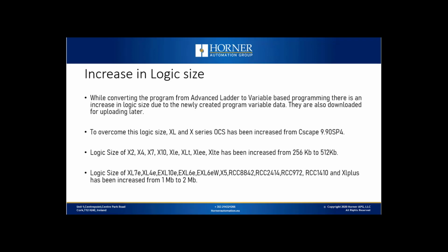While converting the program from Advanced Ladder to variable-based programming, there is an increase in logic size due to the newly created program variable data. They are also downloaded for uploading later. To overcome this, the logic size of XL and X series OCS has been increased from Cscape 9.9 SP4.